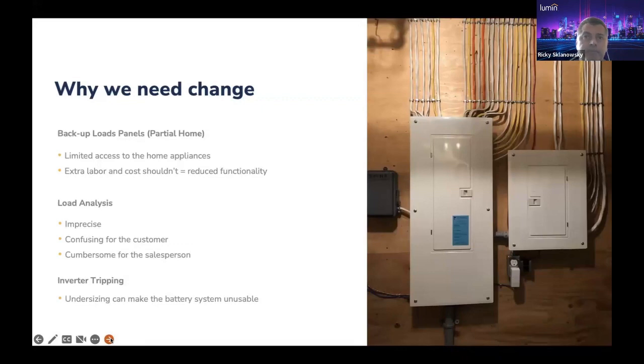On the grid, the customer essentially has a limitless supply of power and energy, so they can conceivably turn on all their loads at once. But when the grid goes down, the ESS becomes the limiting factor for power and energy. With Lumin, you'll never have to worry about an inverter tripping due to overload. Lumin will shut down load such that it's always within the continuous power rating of the battery-based inverter.